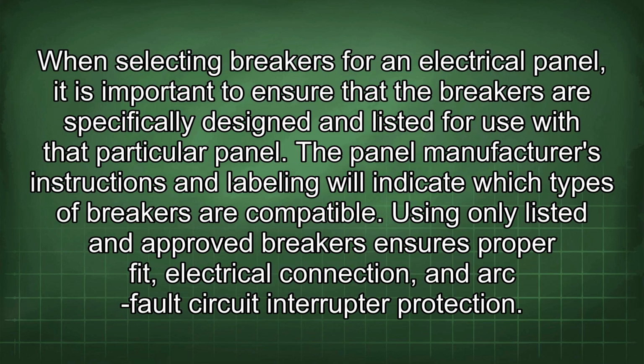When selecting breakers for an electrical panel, it is important to ensure that the breakers are specifically designed and listed for use with that particular panel. The panel manufacturer's instructions and labeling will indicate which types of breakers are compatible. Using only listed and approved breakers ensures proper fit, electrical connection, and arc fault circuit interrupter protection.